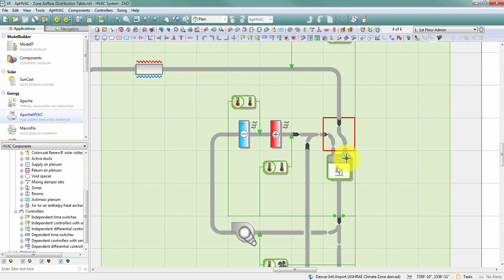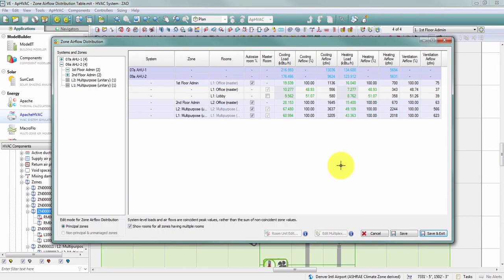The dual inlet supports distribution of ventilation air to spaces within a zone when that distribution needs to differ from the heating and cooling airflow distribution from the fan coil unit. This is only used when ventilation air is separately ducted into spaces and not combined with conditioning air. As a result of adding the dual inlet, the zone airflow distribution table now has two new columns: ventilation airflow percentage and ventilation airflow volume.